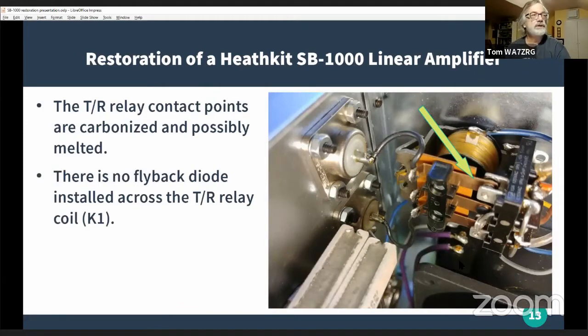This is actually the TR relay. The contact points on the TR relay are oxidized and carbonized, and some of them look like they might even have been melted. But I got in and inspected it closer - they were okay, and I was able to use some emery cloth to clean the contacts on the relay. You'll notice this one contact had bent all the way out - I straightened that.